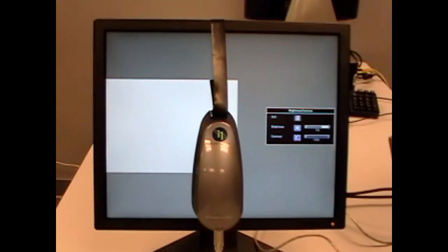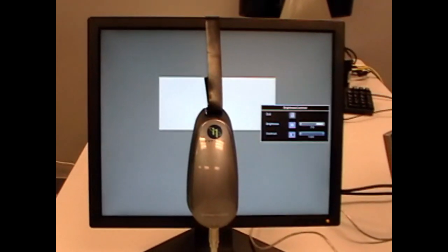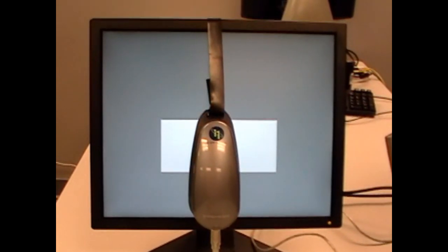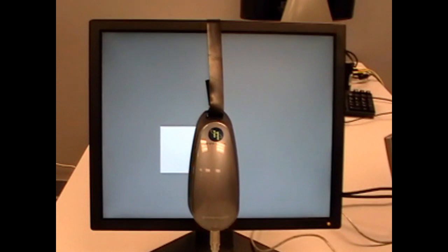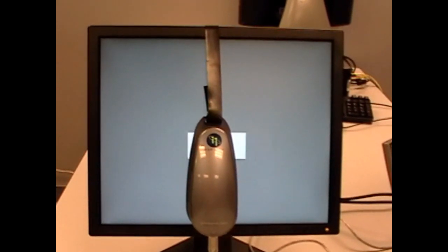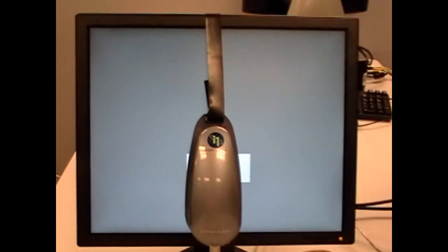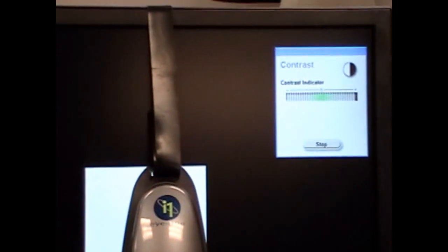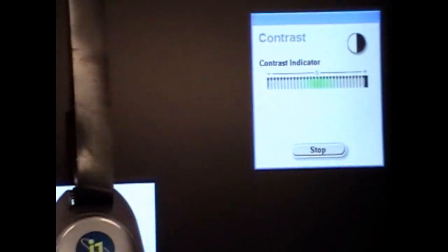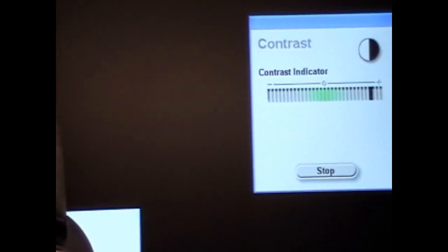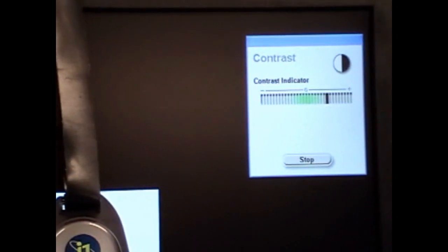And at this point, the screen is locating the device. It searches it out using a difference in brightness. It throws a box around it, and it locates the instrument. Once it locates the instrument, it's all right to just move this instrument a little bit so that it's right in the center of that box.